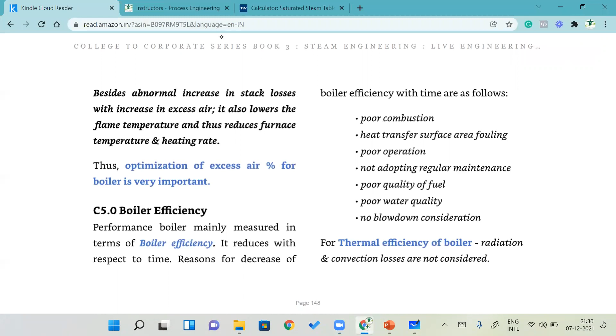And now, see, most of the time boiler efficiency is going to be affected because of poor combustion. When the fuel is not combusting well, when the fuel is not completely combusted, partial or incomplete combustion, such things will happen, and that is going to affect it. And heat transfer surface area fouling. If you don't use pure water, fouling can happen, and that fouling is going to reduce the heat transfer.